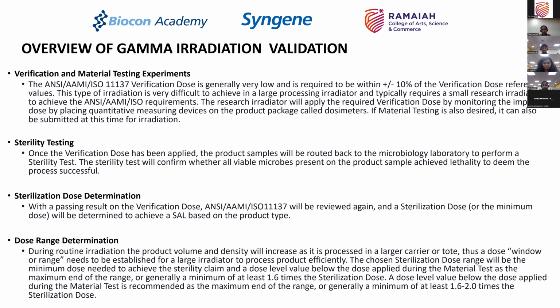Verification and material testing. So now, what happens is that once you have a verification dose in the ANSI standard, when you look it up, the verification dose is generally very low and is required to be within plus or minus 10% of the verification dose reference values. This type of irradiation is very difficult to achieve in a large processing irradiator, and typically requires a small research irradiator to achieve the ISO requirements.